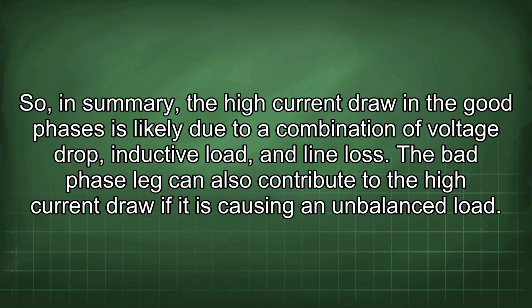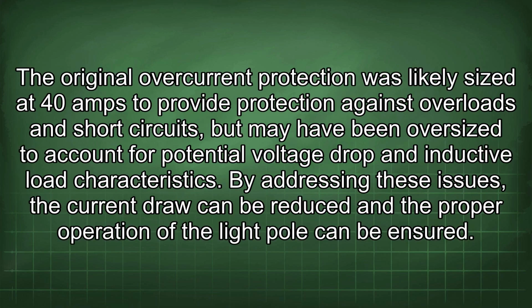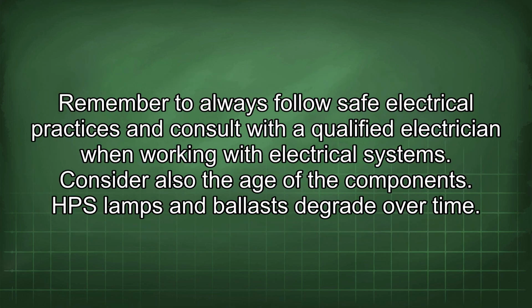The bad phase leg can also contribute to the high current draw if it is causing an unbalanced load. The original overcurrent protection was likely sized at 40 amps to provide protection against overloads and short circuits, but may have been oversized to account for potential voltage drop and inductive load characteristics. By addressing these issues, the current draw can be reduced and the proper operation of the light pole can be ensured. Remember to always follow safe electrical practices and consult with a qualified electrician when working with electrical systems.